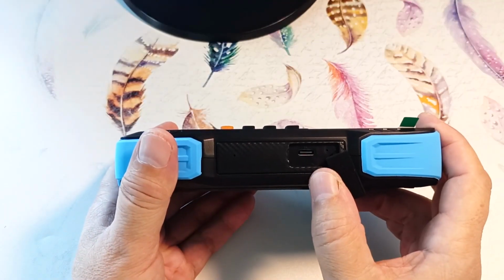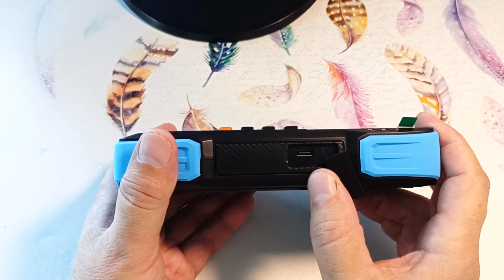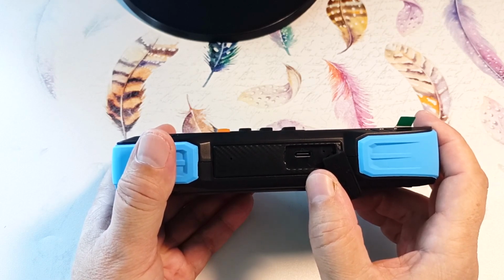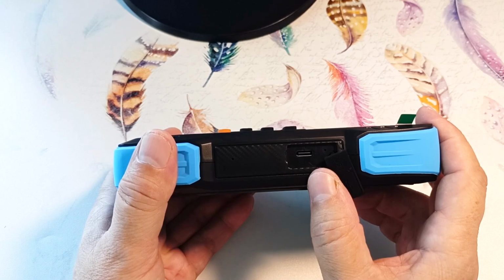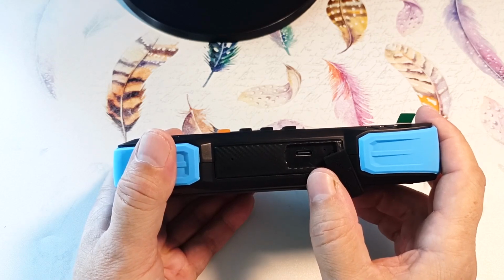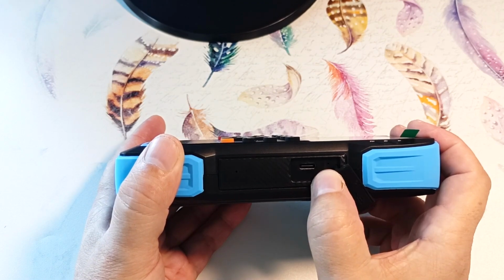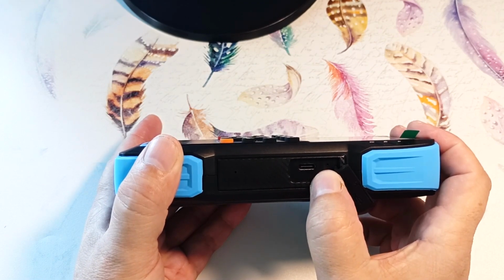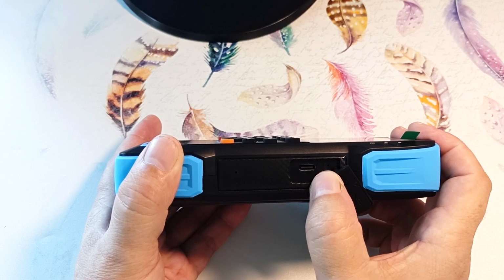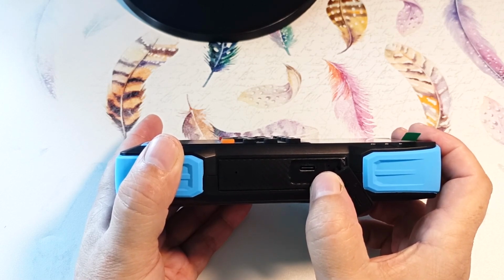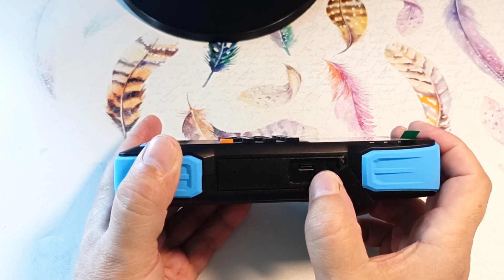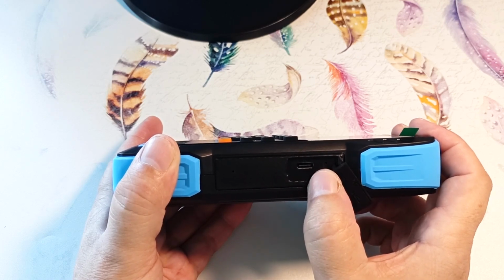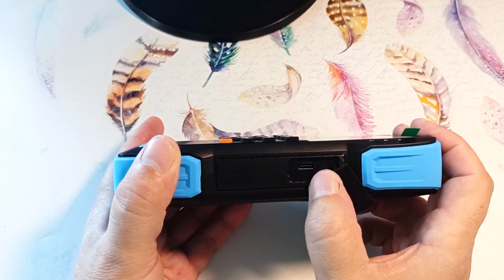On the side, behind a rubber plug, there is a Type-C input, with which you can charge the device, change its firmware, or upload saved waveforms to a computer. The charge indicator is visible through this hole and glows red when charging. Inside the device there is a lithium battery with a capacity of 3000 mAh, and the operating time can reach 6 hours.